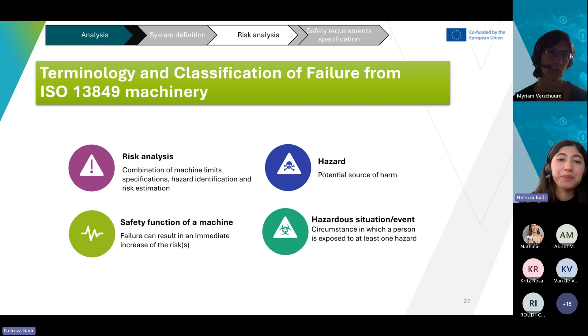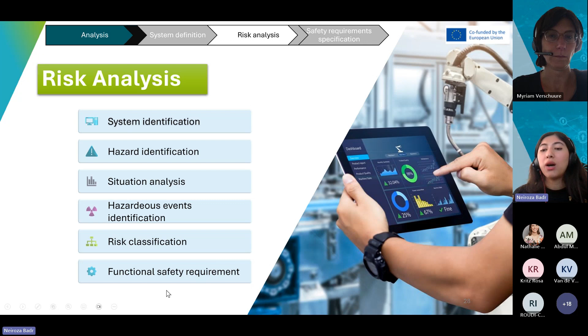So functional safety is a build-up process. First, we start by defining the overall system we have, our functions, the architectures, all the elements we need for the risk analysis of the system. The next step is to identify the possible hazards related to these functions and elements, by listing and identifying all the possible situations. After that, we think about all possible hazardous events that could occur due to these hazards in specific situations. Then comes the assessment and classification of the risks that we're going to see in the next slide: how classification is performed according to the ISO 13849 standard for machinery. The purpose of this risk analysis is also to allow the creation of functional safety requirements.